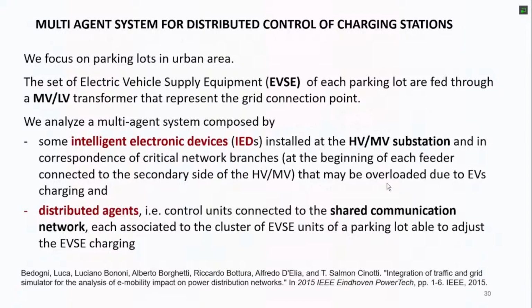So we can think of a device in the substation that measures the overloading, the current in the transformer or branch, and a control unit in the parking lot that receives a signal from that device telling it to decrease the power to a charging station. In general, these charging stations can control their maximum power: rated at 50 kilowatts, but they can also operate at 40, 30, or 20. So there's the possibility to limit the power. This control in the parking lot can decrease the maximum power of the charging station if there are events in the network, like much other load causing the feeder to be overloaded.